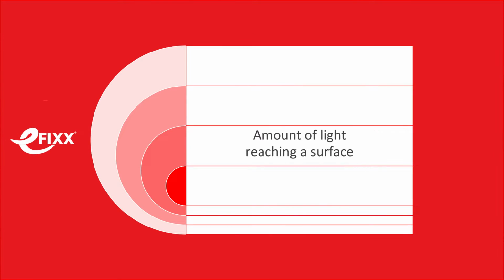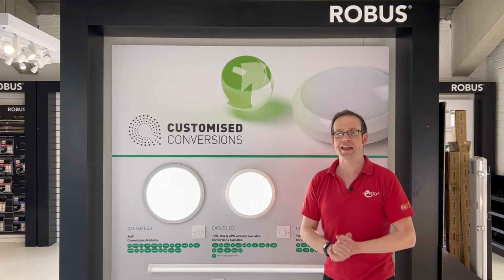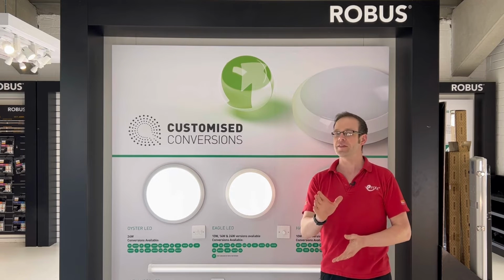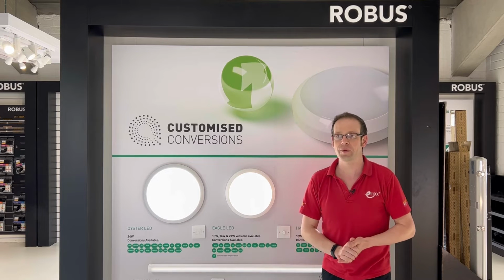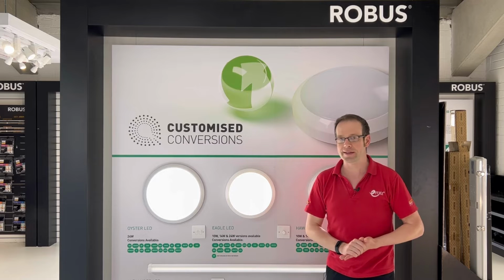So to assess how well lit a surface is, we need another measurement of light, which is called illuminance. This is measured in a unit called Lux, and this is the starting point of a lot of lighting design, as it is often a target to aim for when choosing how many lights to install. We'll have a look at how all these units tie together as calculations in a moment, but first there's a couple of other ways of describing light with numbers that will impact on lighting designs.